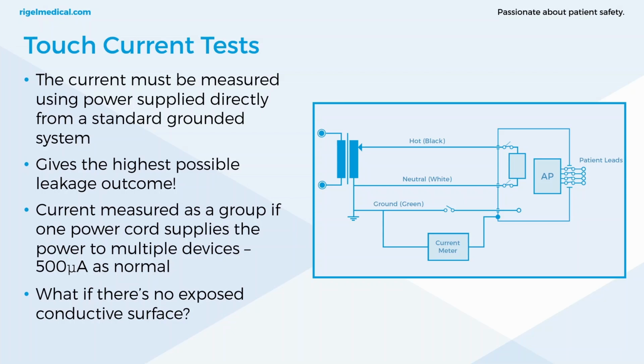There are also then suggested methods of lowering the sum leakage if you're getting higher than expected values. So if it's above that limit, you can then separate the device grouping. But it's only required, obviously, if the values exceed that value. So it does save you a lot of time. If you've got a stack system, you measure it as a group. If it falls under that total leakage limit, it certainly saves you a bit of time.